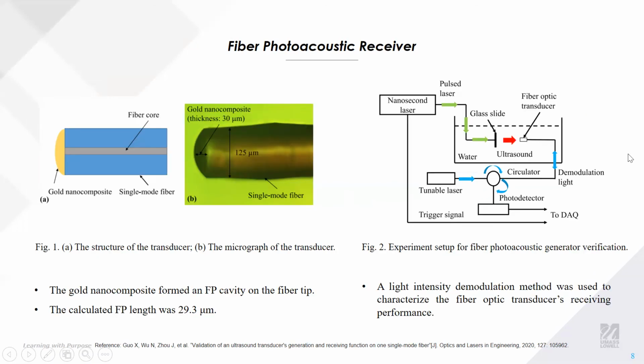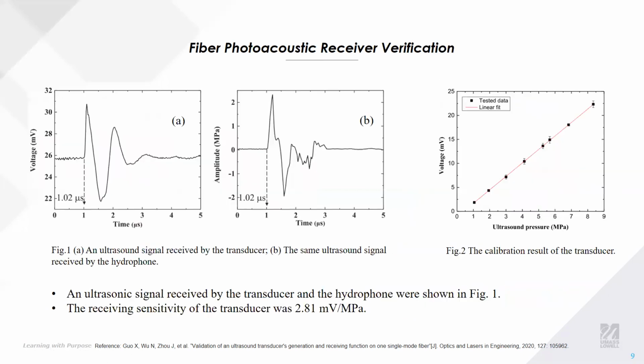By the way, after we used the fiber optic transducer to receive the signal, we replaced it with a hydrophone in the same location, and then we compared the results from the fiber optic transducer and the hydrophone. Figure A is the signal from the optical fiber transducer, and figure B is the signal from the hydrophone. And the next figure is the comparison result. The calibration result shows that the transducer sensitivity was 2.81 millivolts per megapascal.